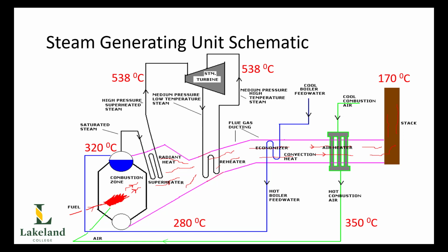Now from here, as our steam enters back into the beginning of the intermediate pressure stage of the turbine, it is now going to expand through the remaining stages of the turbine. That is, the intermediate pressure stage and the low pressure stage of the turbine. By doing this, we avoid getting condensation in the low pressure stage of our steam turbine by reheating it, and also putting more enthalpy back into the steam so we can extract more useful work energy out of our steam turbine that'll probably be driving an alternator producing electricity.